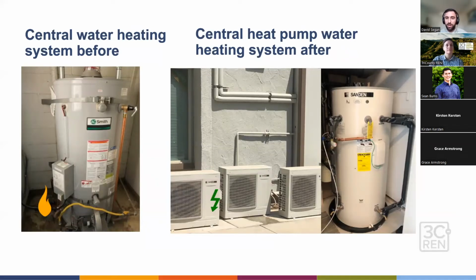Another water heating system is your central system, serving multiple apartment units. On the left is, again, the natural gas tank type central water heating system, and on the right is a heat pump water heating system. This is a little different than what we saw previously, where it's an integrated heat pump water heater. Here we have a split central heat pump water heating system where the heat exchangers will be outside, so no concern about intake air and exhaust. And the tank is inside, and you just pipe the hot water from the heat exchangers to the tank.